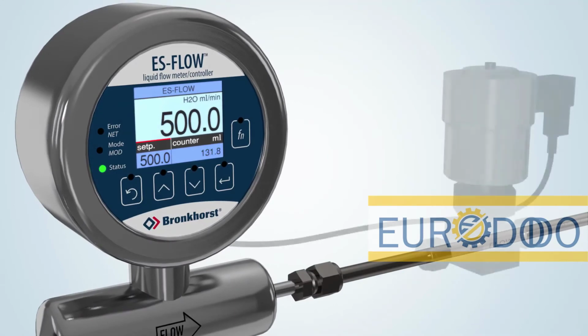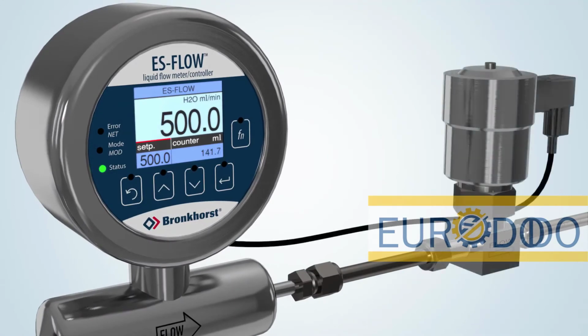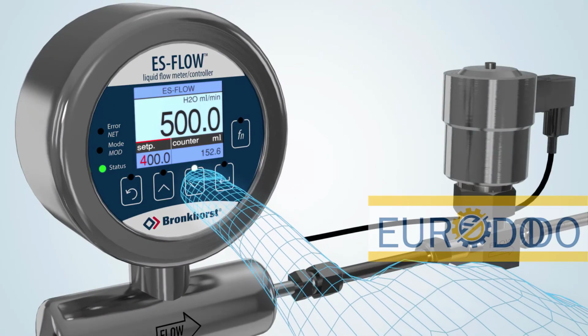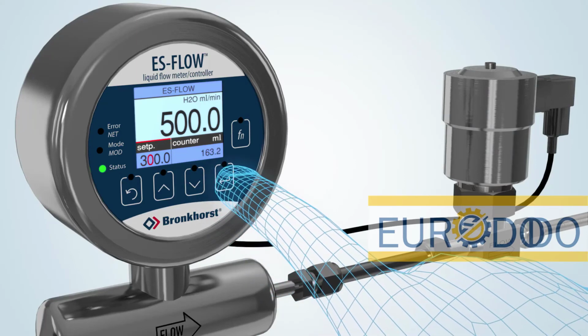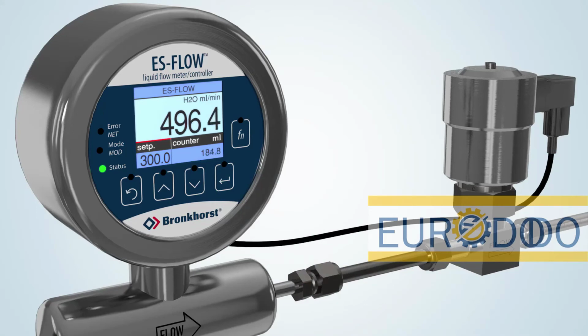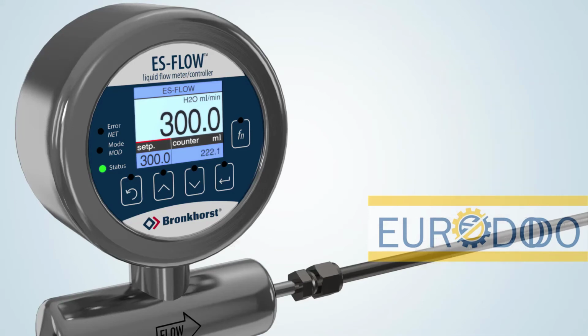Alternatively, the ES-FLOW flow meter can be combined with a control valve to constitute a compact control loop. Upon receipt of the new set point value, the PID controller changes the current of the electromagnetic coil of the control valve, followed by instant adjustment of the liquid flow.